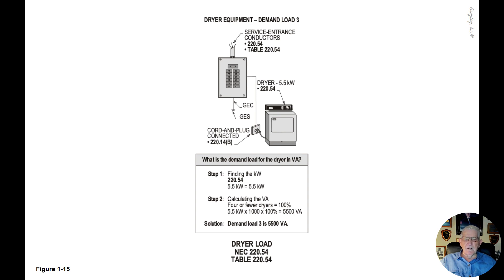The boxed question asks: what is the demand load for the dryer in VA? Step one — find the kW. Per NEC 220.54, for four or fewer dryers the minimum is 5 kW, but since the nameplate is 5.5 kW, we use 5.5 kW. Step two — four or fewer dryers are taken at 100%, so 5.5 kW times 100% equals 5.5 kW.